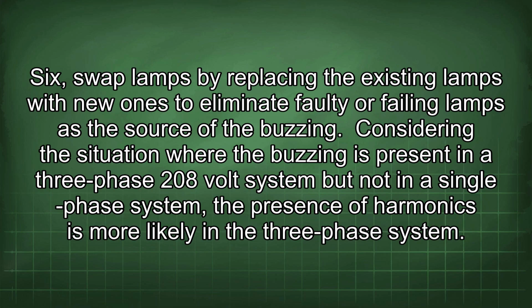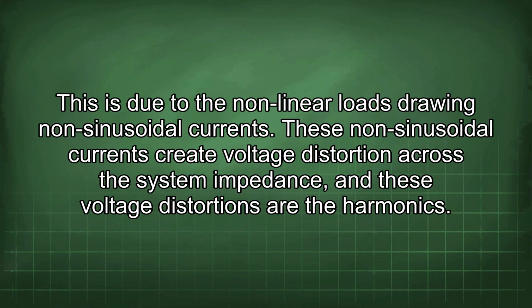of the buzzing. Considering the situation where the buzzing is present in a three-phase 208-volt system, but not in a single-phase system, the presence of harmonics is more likely in the three-phase system. This is due to the non-linear loads drawing non-sinusoidal currents. These non-sinusoidal currents create voltage distortion across the system impedance, and these voltage distortions are the harmonics.